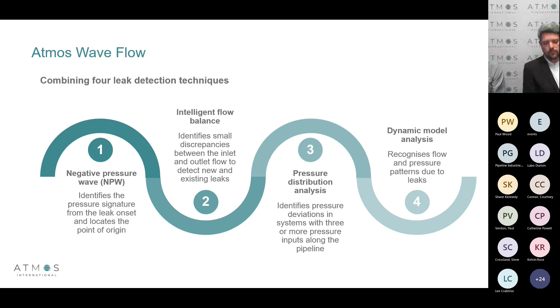Now, if you can install flow meters or you have flow meters available on your pipelines, then we can combine this with an intelligent flow balance. What's useful about utilizing flow meters is it allows you to detect new leaks that might be forming over a longer period of time, but you also have the advantage of being able to detect existing leaks on your network. If you can put more instrumentation down the pipeline, so the more hardware you have, the better the performance of the system, you can then do pressure distribution analysis. And when we talk about pipeline leak detection, especially when we're looking at the internal properties of the pipeline, so flow, pressure, temperature, it has a very unique pattern to it. So when our technology detects these changes in flow and pressure, we can alarm very quickly.